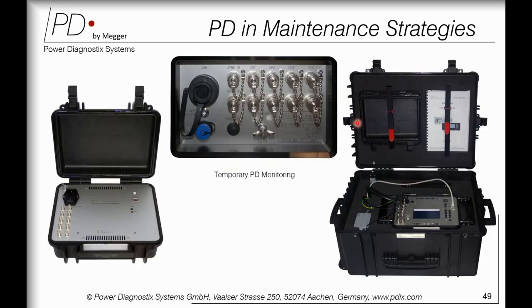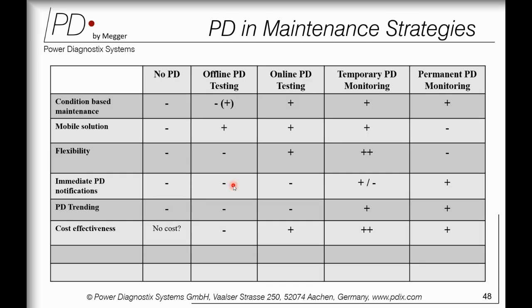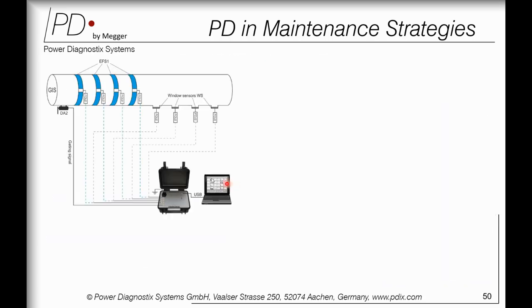When you talk about temporary PD monitoring, we are offering the GIS Monitor Portable, which is a great tool for it. This portable instrument will help you do partial discharge measurements in your GIS, spot measurement as well as temporary monitoring. It means you can do the monitoring feature with the same portable kit. This is the easy setup. You can see this is my GIS Monitor Portable connected with my laptop, and here my sensor has been connected either with the inbuilt UHF sensors or with external flex sensors where you don't have inbuilt UHF sensors.